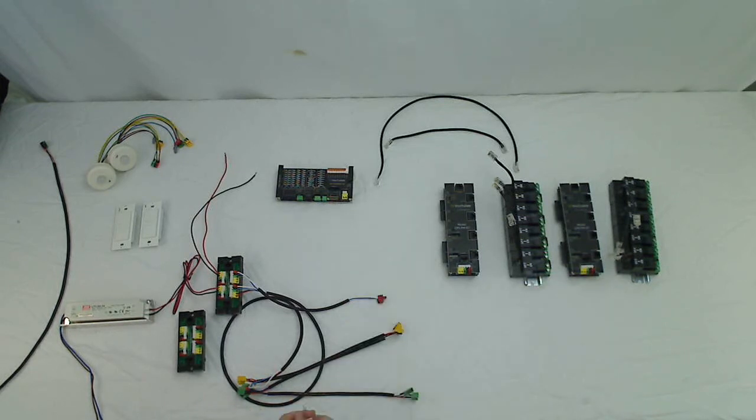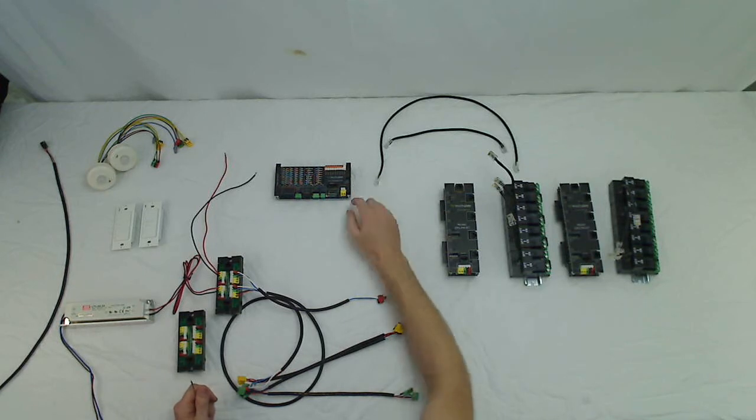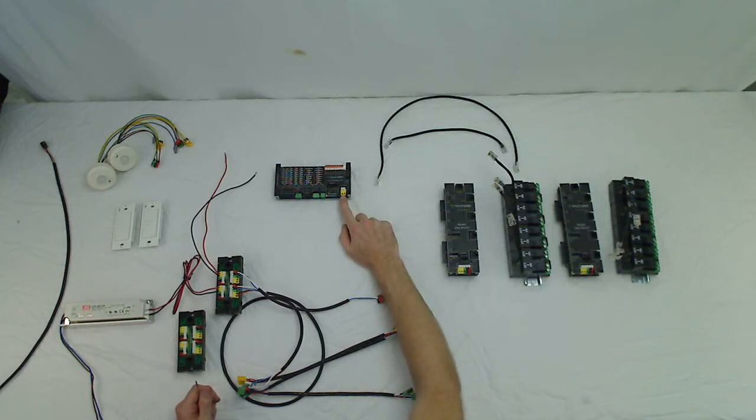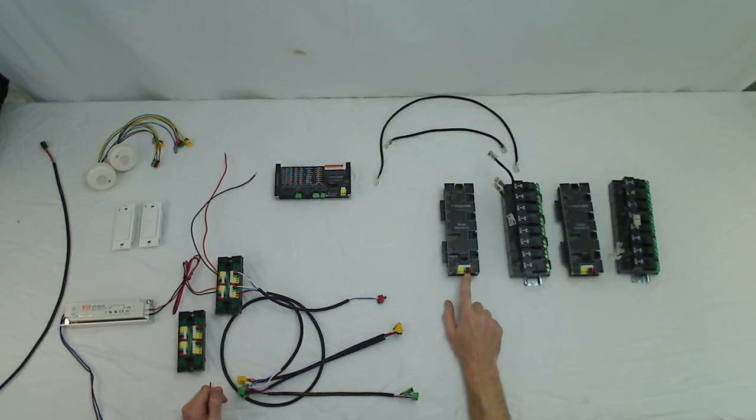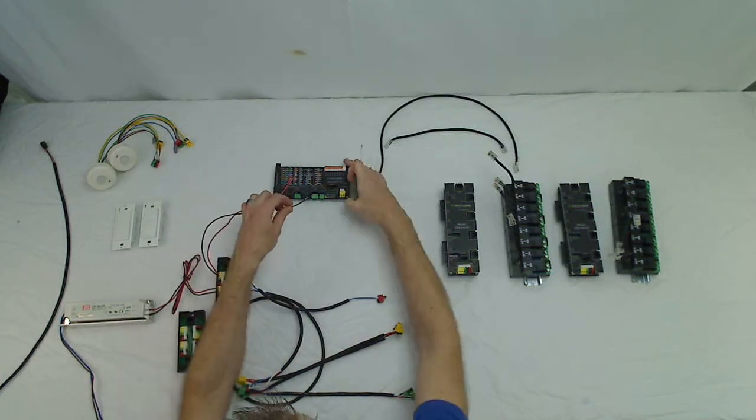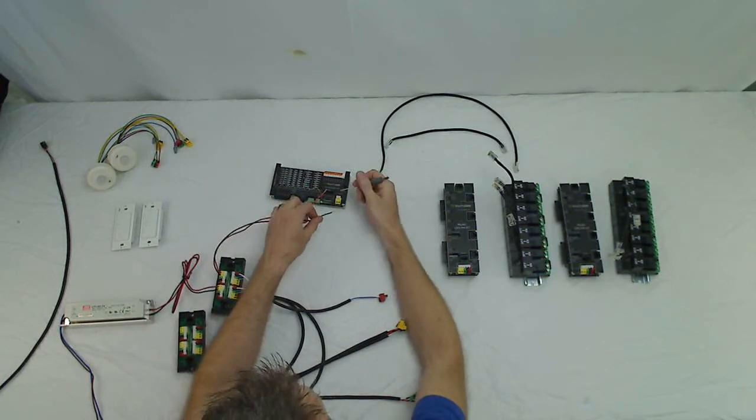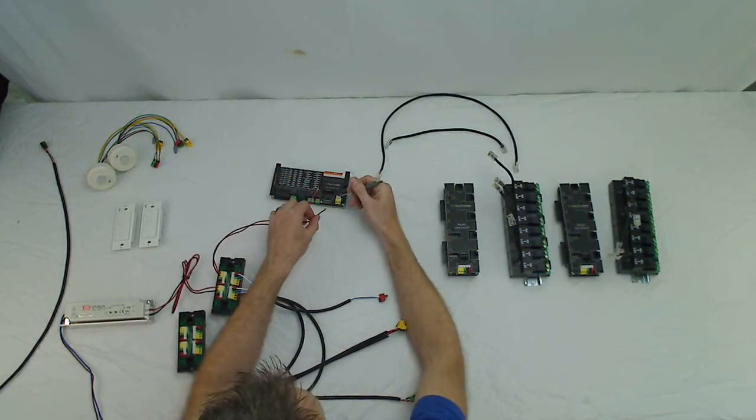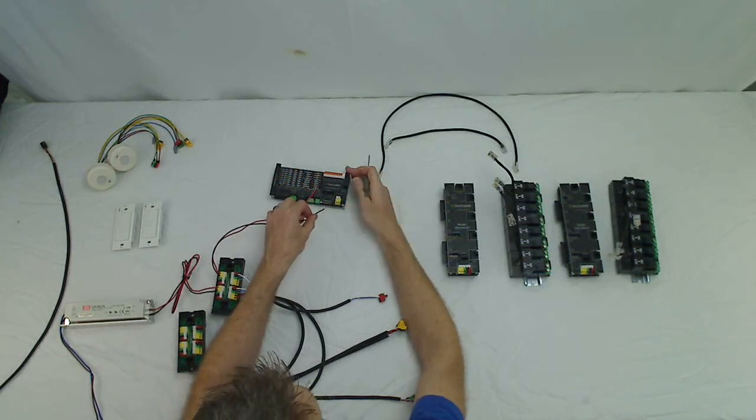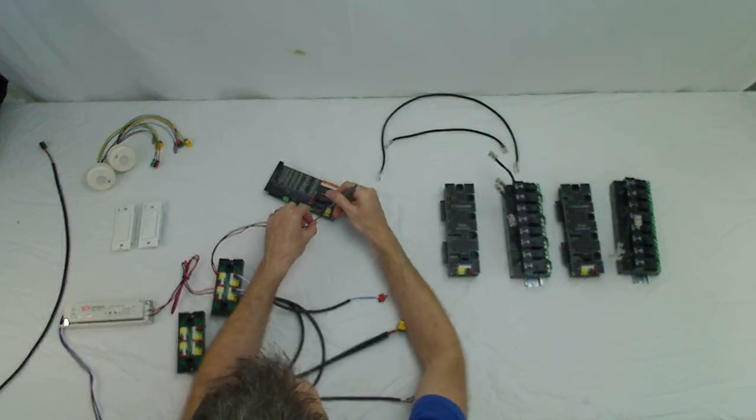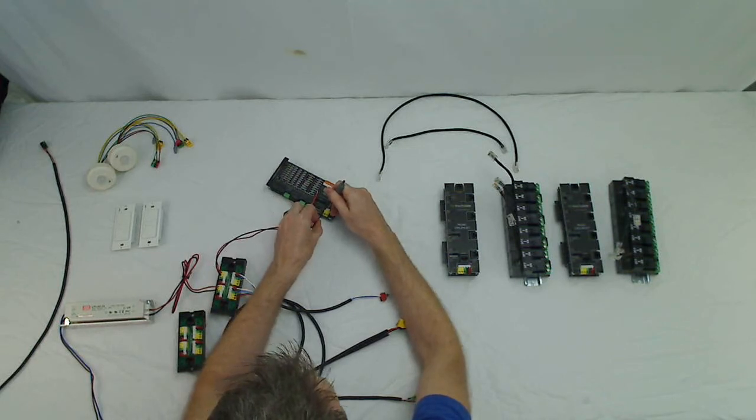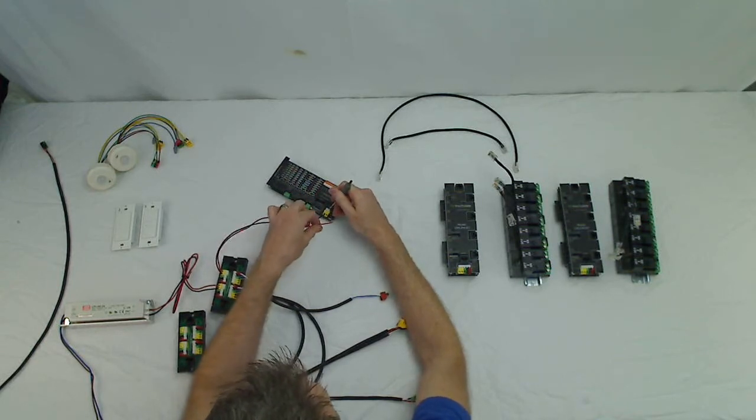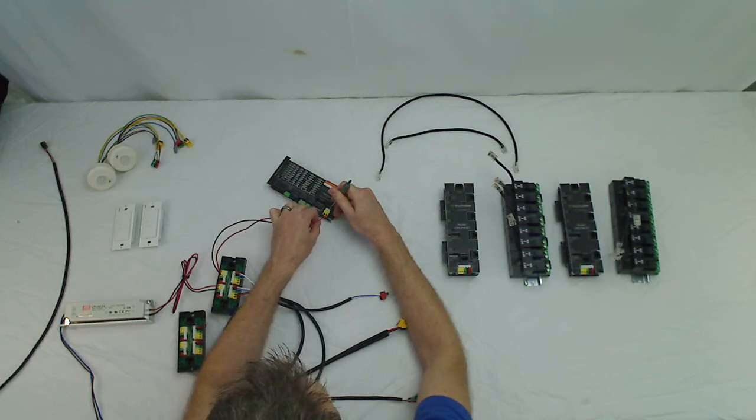So to begin, the first thing we need to do is bring power to our lighting controller. It's the yellow spring-loaded dinkle connection here at the bottom. All of our connections for power on touch-plate devices are yellow. And all of our communications are green black red. All of the yellow power connections are not polarity sensitive, so it does not matter which side positive and negative go on. You just need to land your positive and your negative.